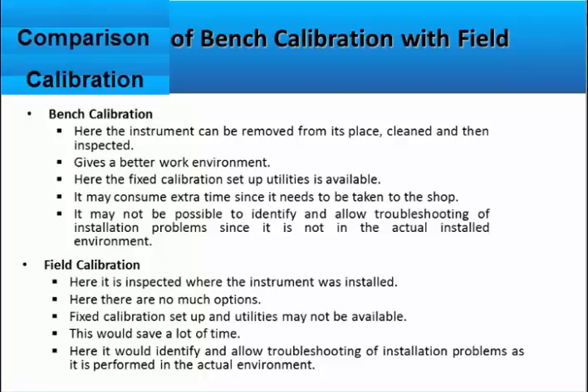Field calibration tends to be a little bit less scrutinised, and is usually tested to a wider tolerance level, mainly because you may not have the ability to check it against a very high standard instrument. Field calibration is one of the most commonly used, mainly for non-critical systems and non-critical instruments, and often ones used in process control, because removing them and taking the whole point out of service becomes an onerous part. So it saves a lot of time to do in-field calibration, but you're generally compromising the standards.